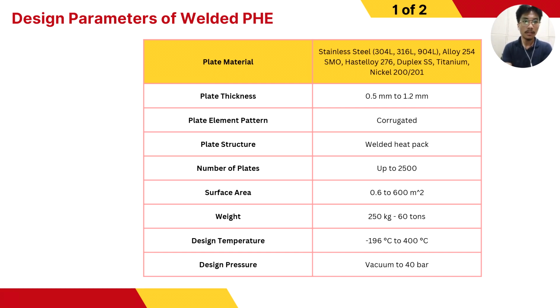Next up is the plate element pattern. So corrugated element or corrugated pattern on the plates. This has lower substance contact points, which promotes more turbulent flow and prevents the accumulation of deposits on the plate surfaces. So these deposits can cause major fouling or rusting if left unchecked. But having a corrugated pattern solves those potential problems.